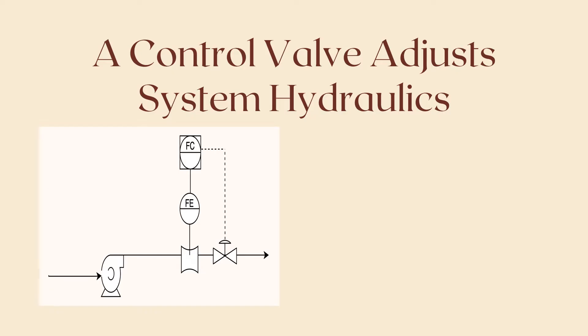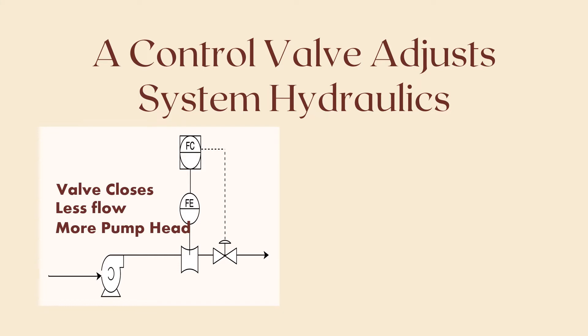The control valve doesn't just act as a final control element, but also adjusts the system hydraulics. Here for example, the control valve acts to adjust the operating point in the pump performance curve, and shifts the system curve to intersect with the pump performance curve, so that we can get the operating point we need.